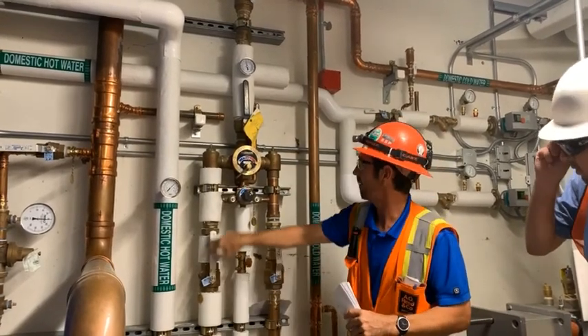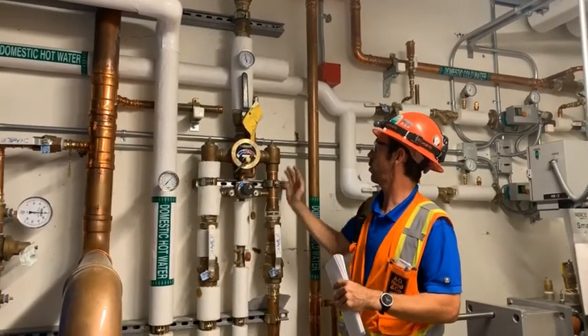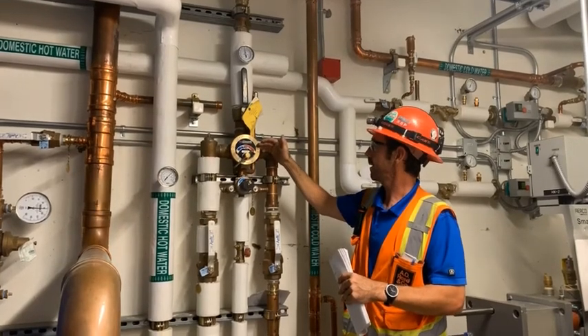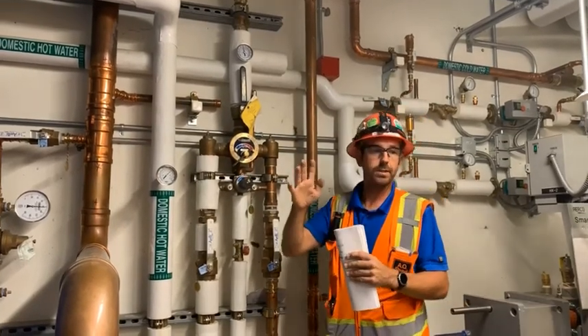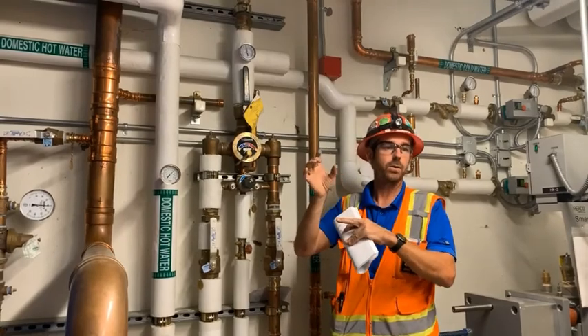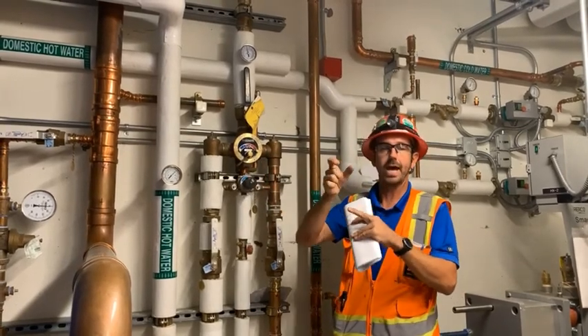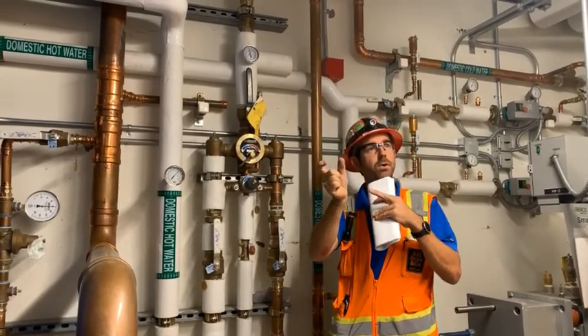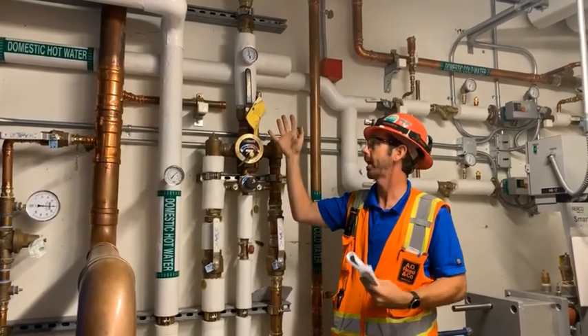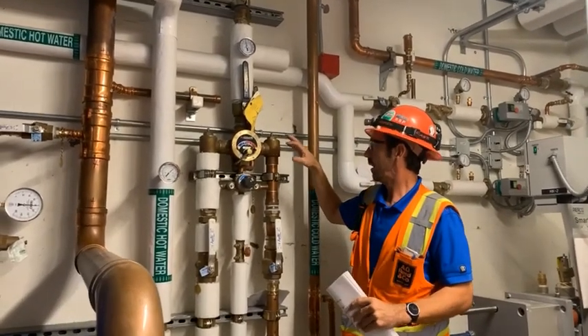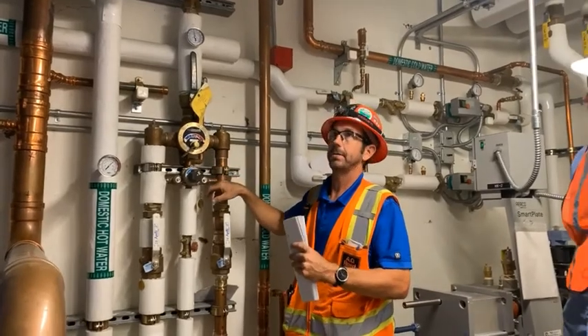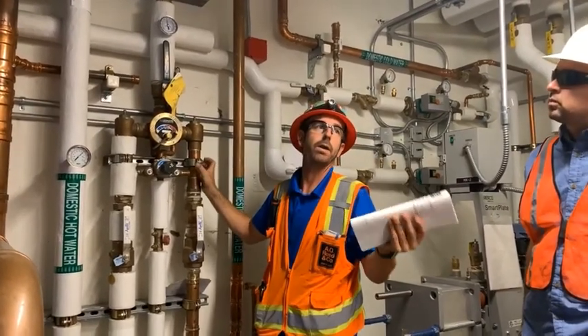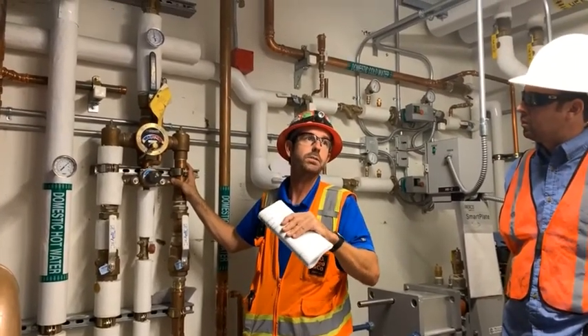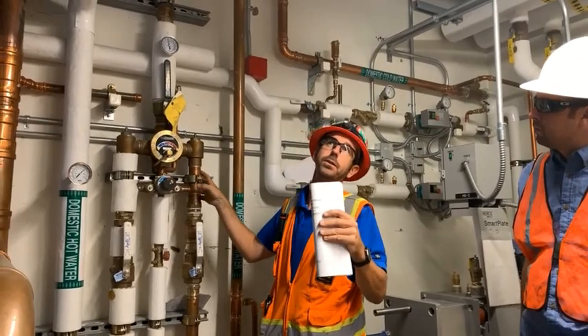Obviously, it's taking hot water from the left, mixing it in the regulator, cold from the right. There's a spring that's calibrated for temperature. So where your set point is, there's a cartridge that'll slide back and forth to give you your outlet temperature, okay? In part of this loop too, to keep hot water in the building to all the fixtures, we have a domestic hot water return loop.